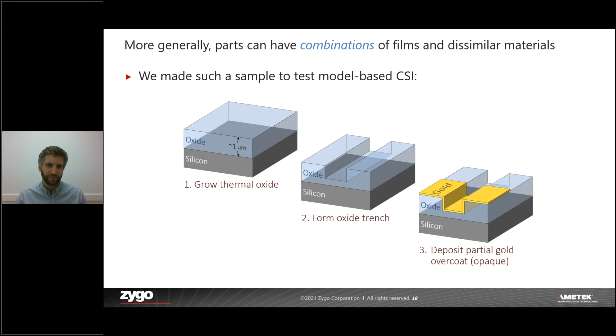And why this is an interesting test is that even bulk materials can confuse conventional CSI. So when you reflect off of a material like glass or silicon dioxide, you get a phase change on that reflection. And the phase change is different than it is when reflecting off of a metal. And in fact, different metals all have unique, different phase changes. And this is important because our system is an interferometer and it measures the phase of the light. And so a phase change on reflection causes a step height change. And this is pretty obvious to anyone who's ever tried to measure a chrome on glass artifact. You'll see that metals tend to appear lower than they actually are.